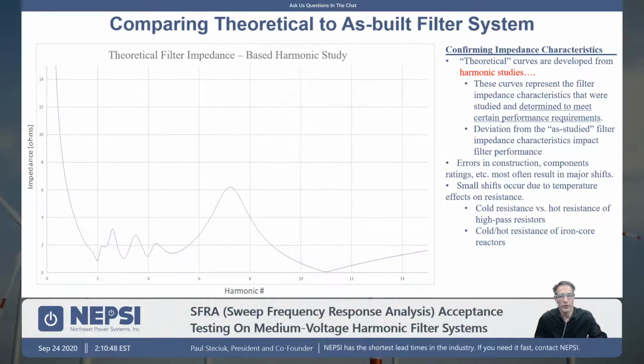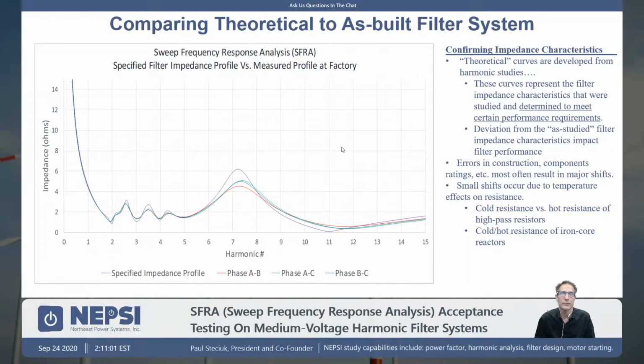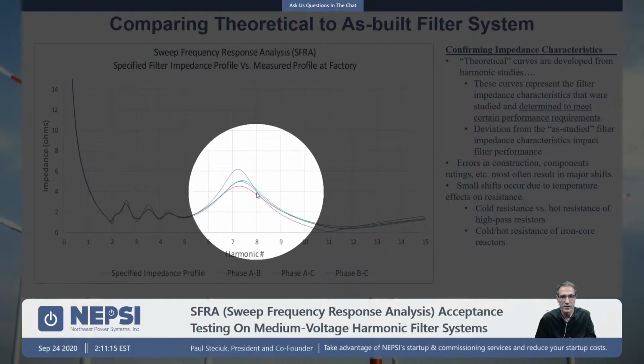And so if we're not involved with the harmonic study, we ask, well, give us the impedance profile that you studied. What is it? We want to see it. And we will overlay that with what we measure in the field. And this is actually for the harmonic filter that I showed on the previous slides. It shows that we can get a very good representation of the filter impedance, and we can reveal that we actually are getting very close results. So we have the 3 phase-to-phase impedance values being compared against the theoretical. And in this case, you can kind of see what the result was.